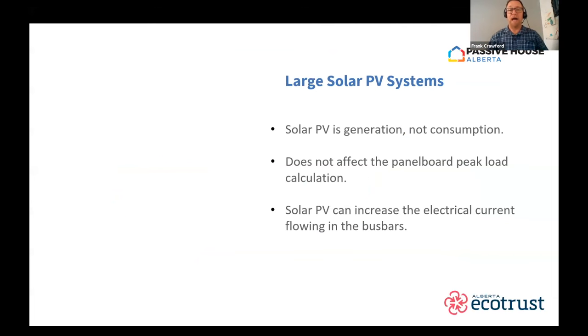So how do we add that large solar panel system? Because if we don't think about it, it can also trigger an electrical service upgrade. And why is that? Before I answer the why, I have to say what the problem is. Firstly, solar PV is generation. It produces electricity. It is not consumption. So a solar system does not affect the calculation of your panel peak load. But solar PV systems can increase the current that is flowing through your bus bars.